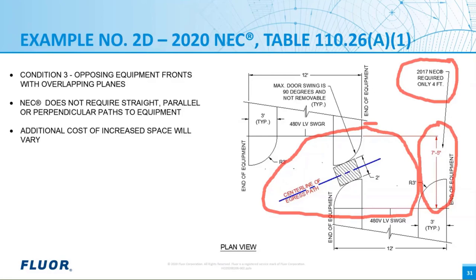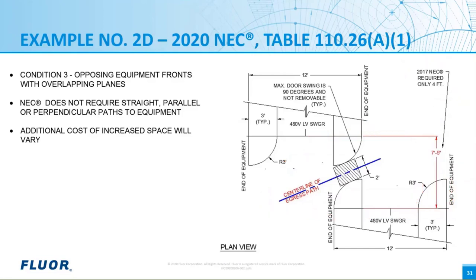Unfortunately, it's really going to be up to the AHJ to determine whether you need the separation of 8 feet, 3 feet plus 3 feet plus 2 feet between the equipment fronts, or if something like this, 7'5" in this case, would be acceptable. This is another possible solution to minimize floor space and meet the words of the NEC without obtaining special permission. Either way, the substation gets bigger, but here the substation would be slightly smaller than with 8 feet.